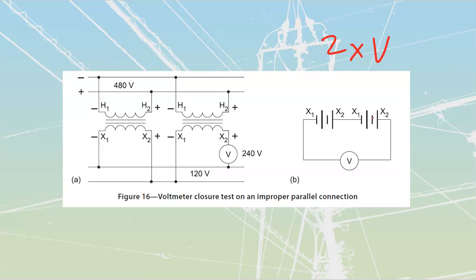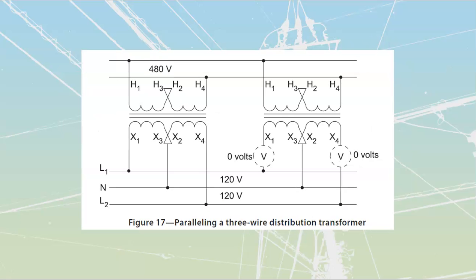It might even be a little more than double the voltage because it's going to have, once again, those magnetizing currents. If I'm doing a 3-wire transformer that I'm paralleling on, I'm going to have to do 2 voltmeter closure tests. I'm going to want to double check both of them. Now, in reality, if I do one test and it checks out all right, the other one should be all right as well. But it's best case always to double check these. Well, let's change this transformer that we have over here as well.